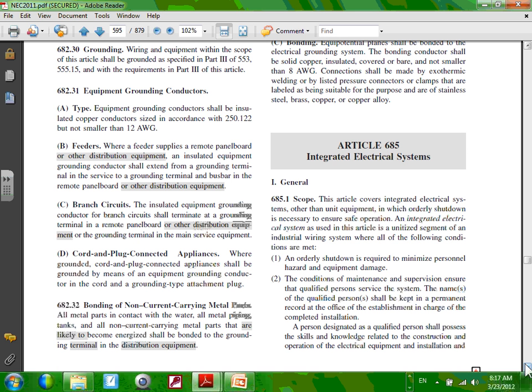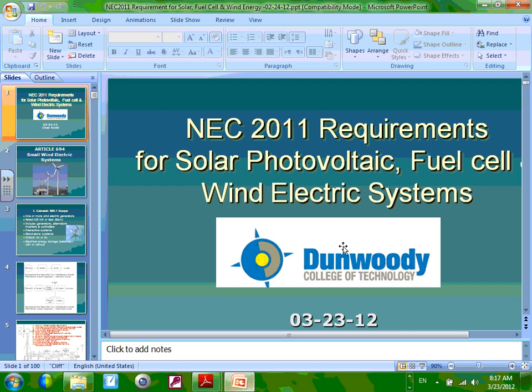And if you lose the grid, a storm knocked out the transformer, what are you going to do? Based on the interactive system, you have to isolate yourself completely from the grid so you can't feed power to the grid and kill the linemen and women fixing the problem, because now you're sending power to the grid. So these are very important articles, because when you tie a generation plant to the grid, you have to have an interactive system. One major protection is that it disconnects you from the grid upon failure of the grid for whatever reason. You lose the power, you isolate yourself from the grid. They do it through the interactive inverter. There are contacts that isolate you from the grid. So I thought I'd just show you these four articles that the presentation is based on.